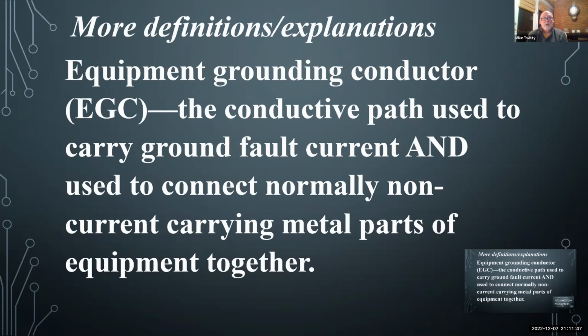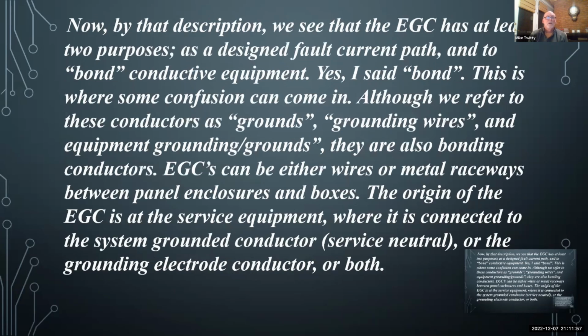Equipment grounding conductors: a conductive path used to carry ground fault current and to connect the normally non-current-carrying metal parts of equipment together. I'm going to go through this next slide quickly to continue with this. By that description, we see that the equipment ground has at least two purposes: as a designed fault current path and to bond conductive equipment. And yes, I said bond. This is where some confusion can come in. Although we refer to these conductors as grounds and grounding wires and equipment grounds, they're also bonding conductors. That's what they're doing from panel to panel. You see a feeder equipment ground going from a service panel to the sub panel downstream. It's bonding those two equipments together and providing a path for fault current.